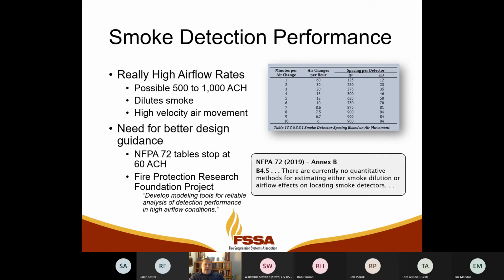To go much tighter than that, we don't have a lot of room for lights or sprinklers or anything in the ceiling. And so we're kind of limited practically at that 125 square foot spacing for detectors. What's being calculated up there, there's 500 to 1,000 air changes per hour in portions of these data centers that have high level containment. Big time dilution of the smoke, high air velocity movement, more than our normal detectors, more than the code really allows us to design to.